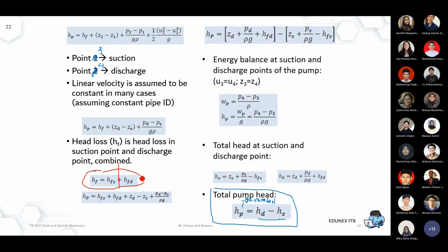I'm already aware that I have friction at the suction part of the pump and at the discharge part of the pump. But actually, I need to be very specific. What will be lost at the suction part and what will be lost in the discharge part? That will affect the NPSH calculation. I need to prevent vapor entering my pump, so it affects the NPSH calculation.